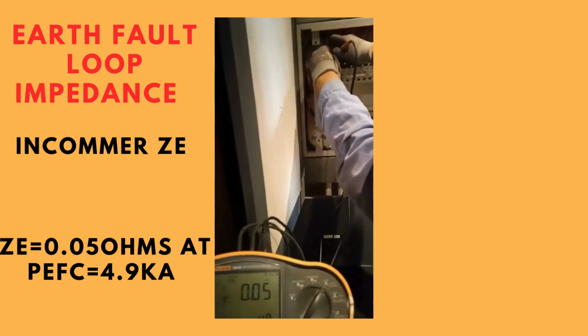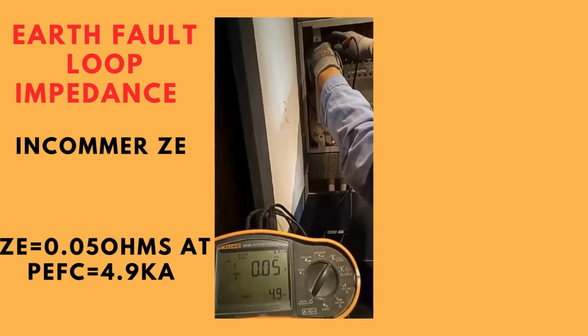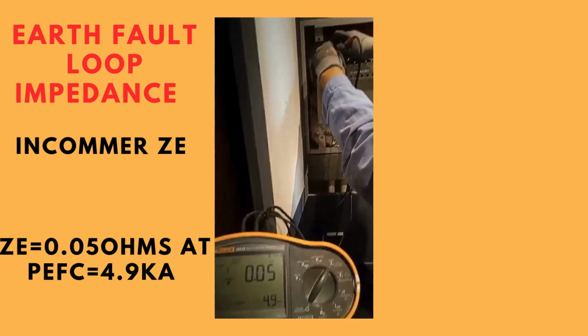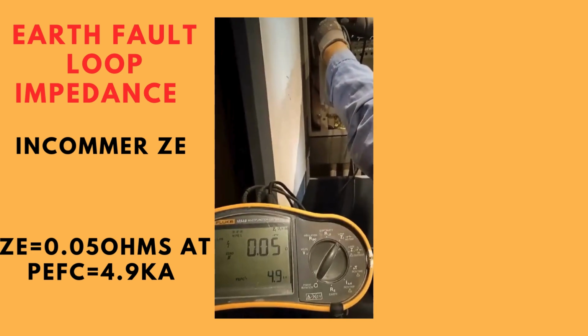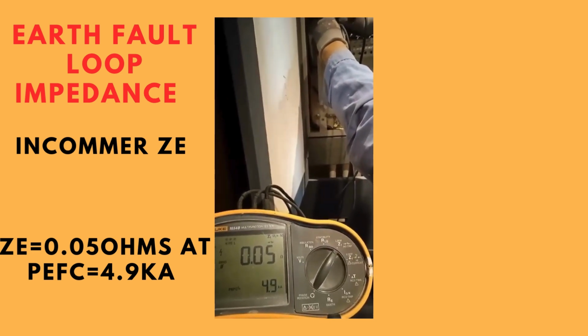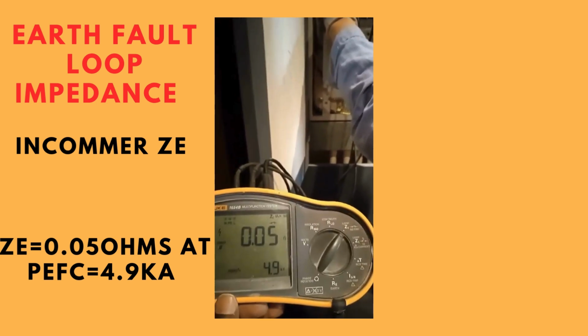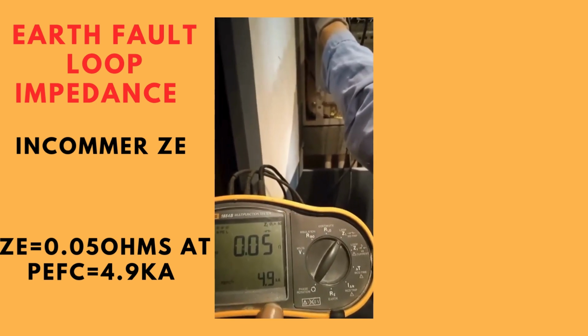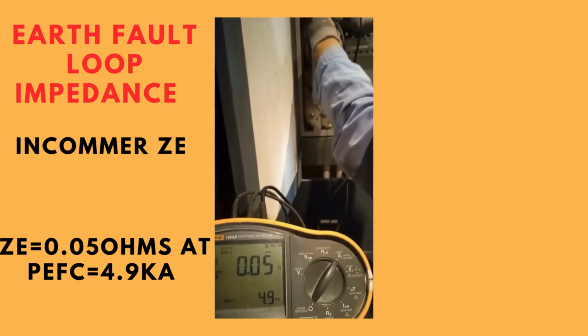Now for the loop impedance test, we test from the external part, which is the incomer. So we have 0.05 ohm. And then if you look down, you see we have a prospective fault current of 4.9 kiloamps.